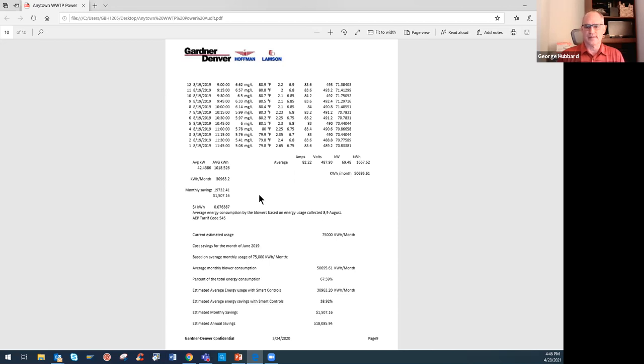The comment I made before was 200, 250 horsepower and higher. The energy consumption of a multi-stage is comparable to some of these single impeller high-speed centrifugals. And a lot of the sites know the multi-stage, they can maintain them, they can repair them, they may repair them locally or they may repair them right on site. It's a known quantity. The high-speed turbos are a little bit of a black box because they come with controls and VFDs, and it's meant to be all packaged together. All the controls and speed control and protection is done by the control system that's with the turbo.